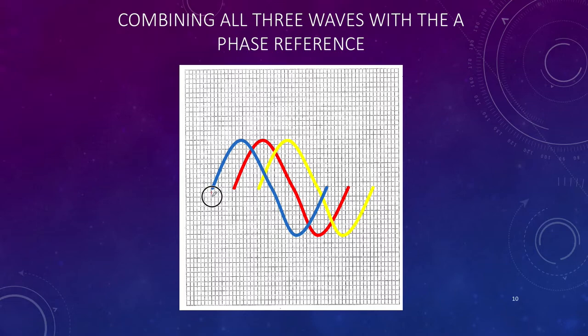The difference here to here is 120 degrees, and the difference here is 120 degrees. If you measure them at any point around here, they're all at 120 degrees separation from each other, demonstrating that our power supply is actually being generated at 120 degrees between A phase, B phase, and C phase.